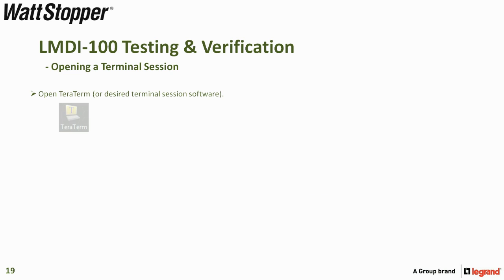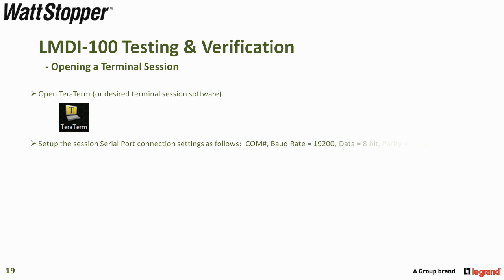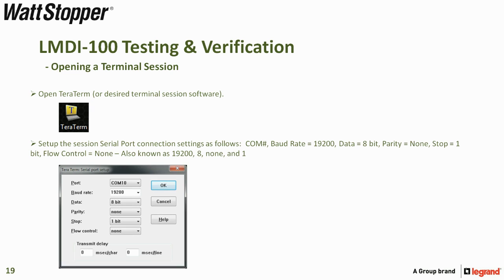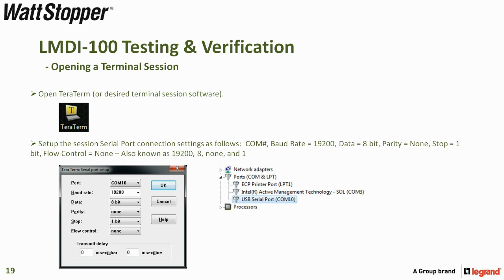Open TeraTerm or your desired terminal session software. Set up the session serial port connection settings as follows: your COM port, baud rate at 19200, data bits 8, parity none, stop bits 1, and flow control none.